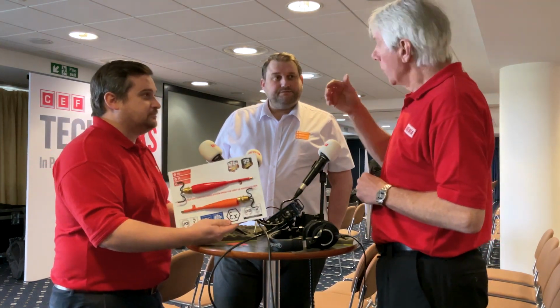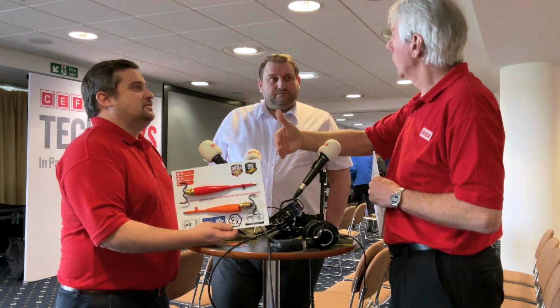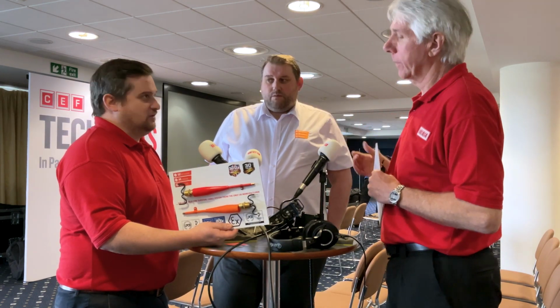It's absolutely great. But is it the case that you don't need to? So that's a judgment call. Or are there categories where you would have to install MICC? Yeah, some of them, hazardous areas, you've got to do it. In hazardous areas, yes, certainly. So you're looking for a cable that's non-passive. The MICC, with the magnesium oxide inside the copper, means no air, water or gas can get through the end of the cable.